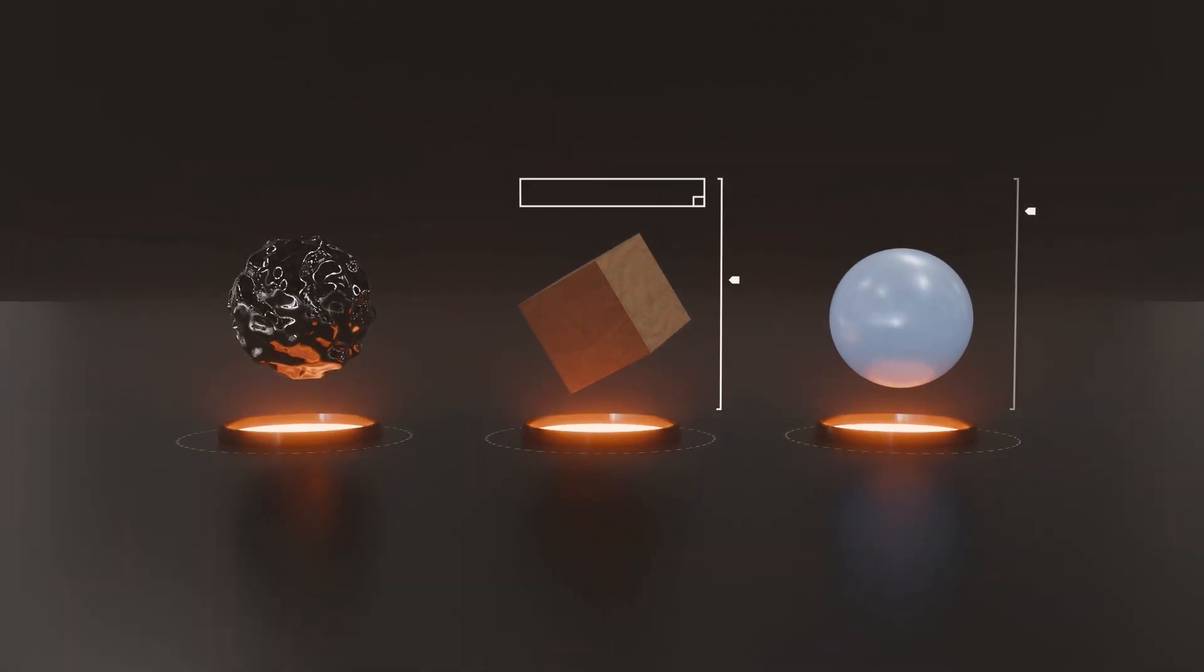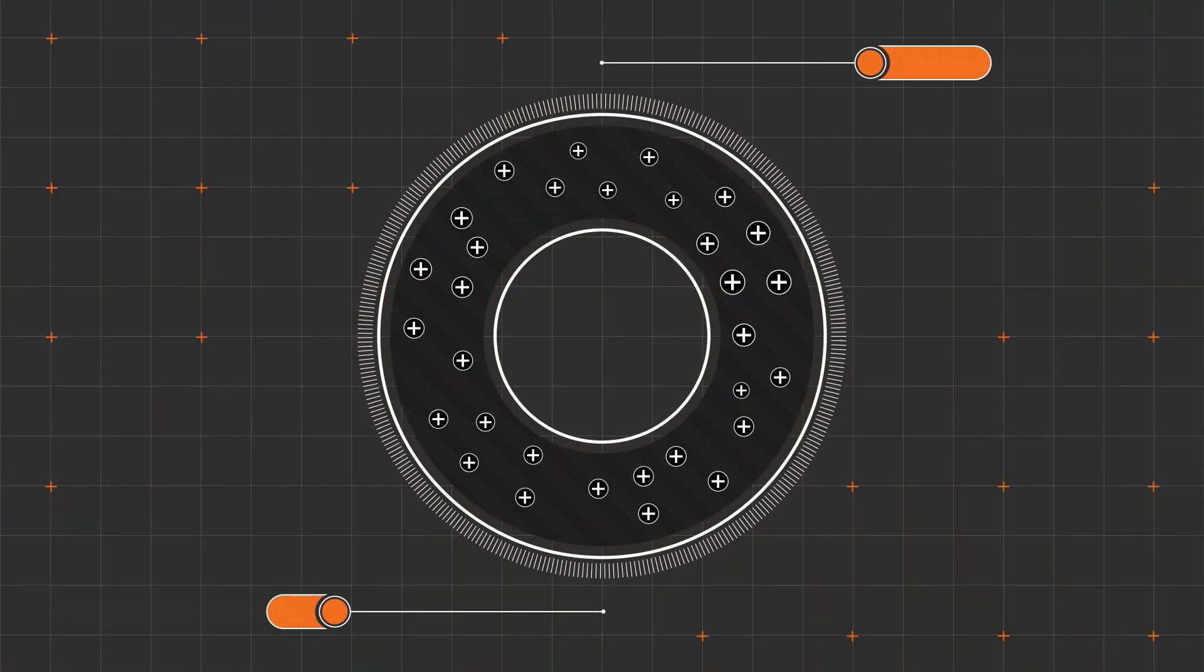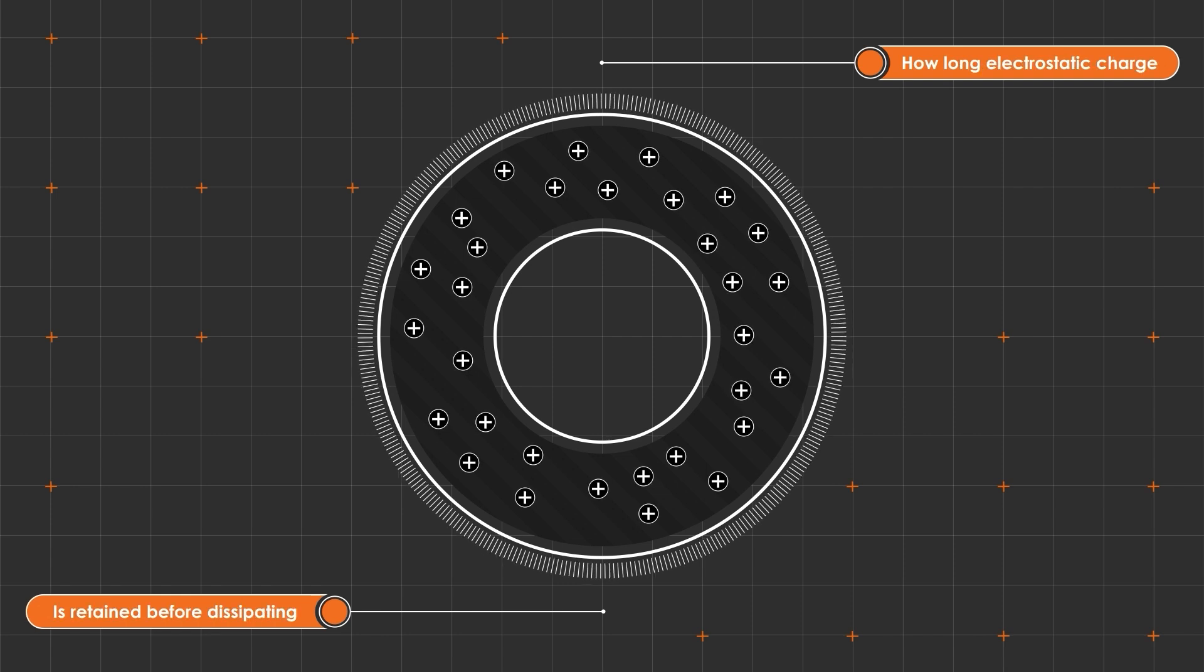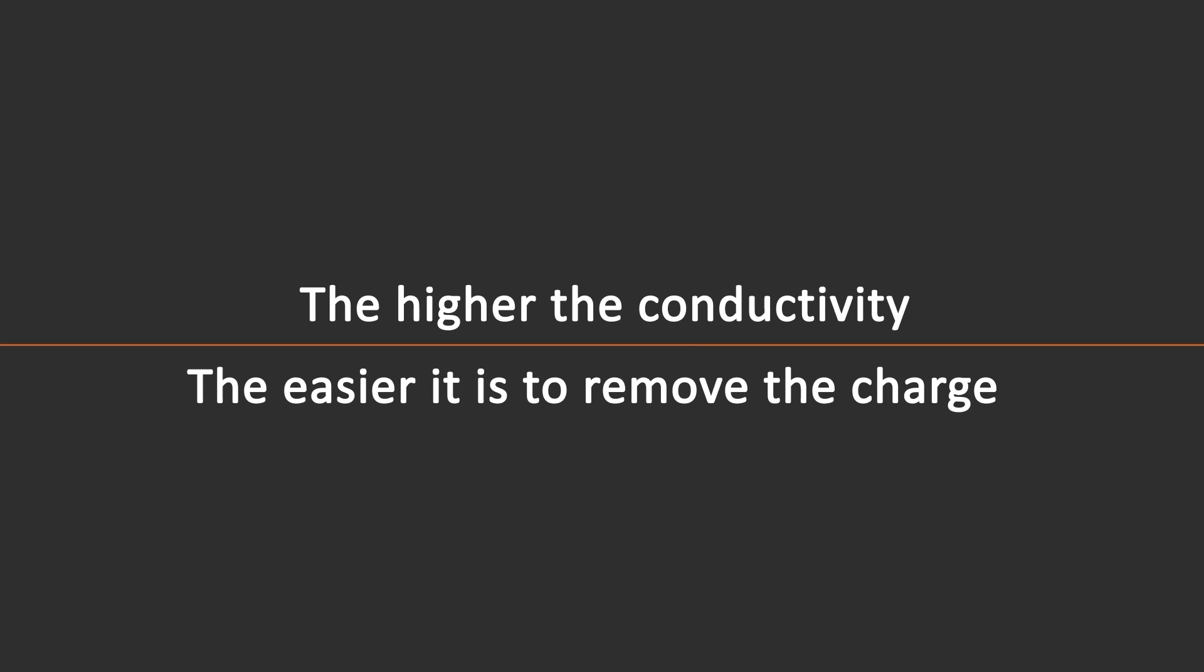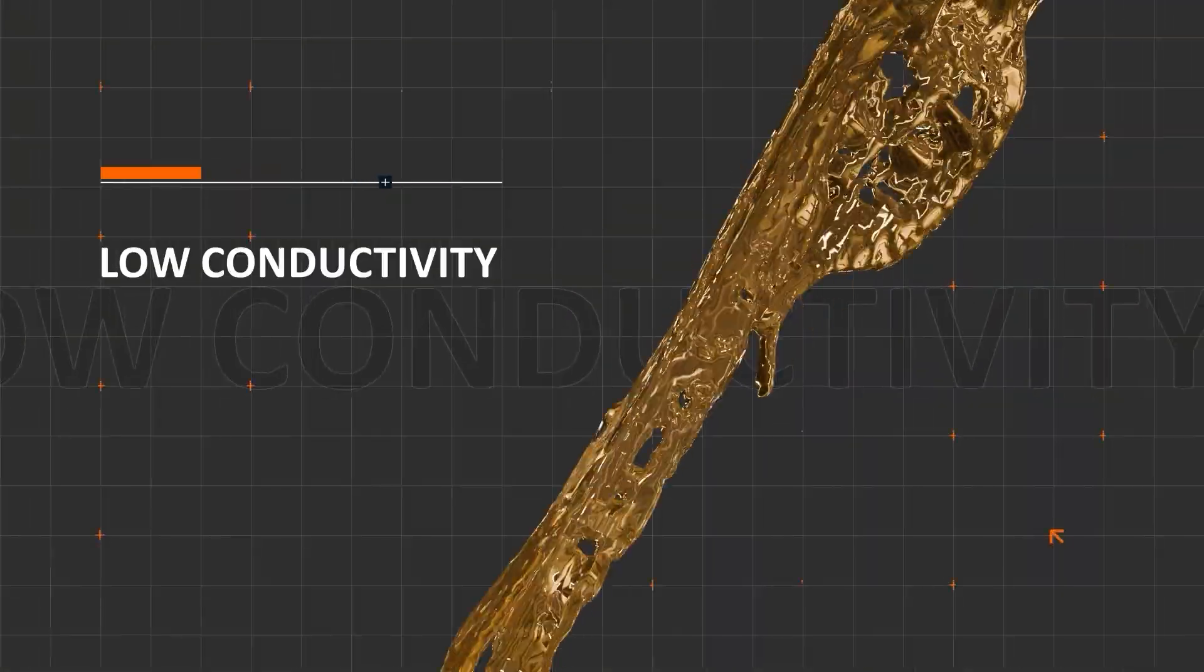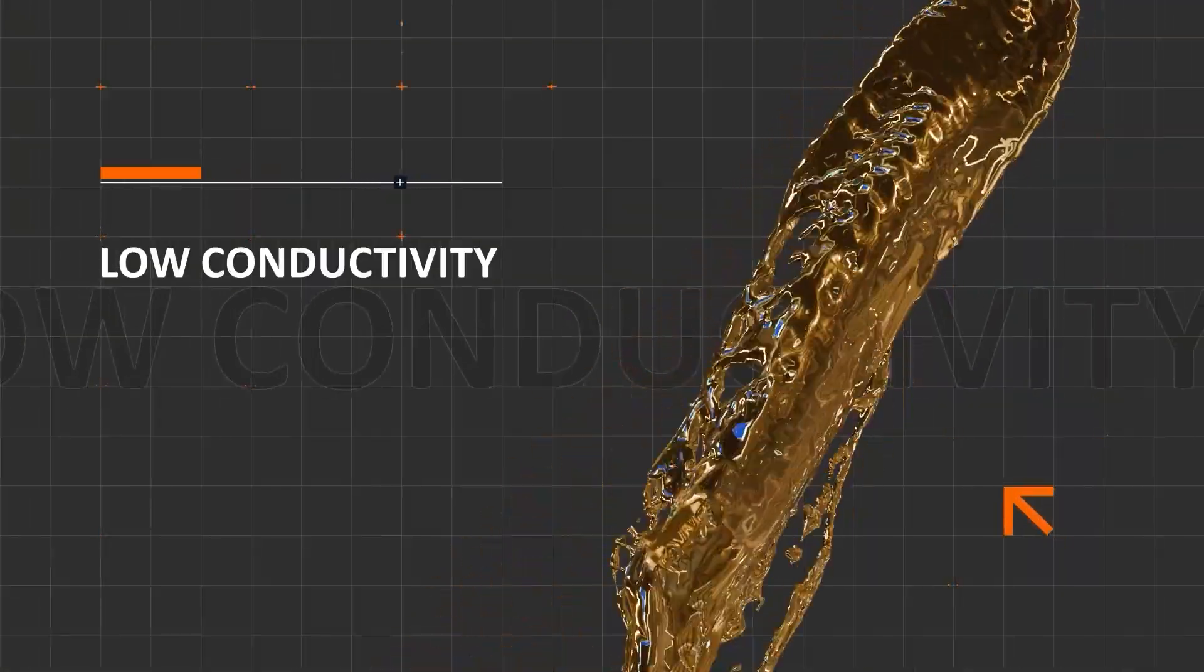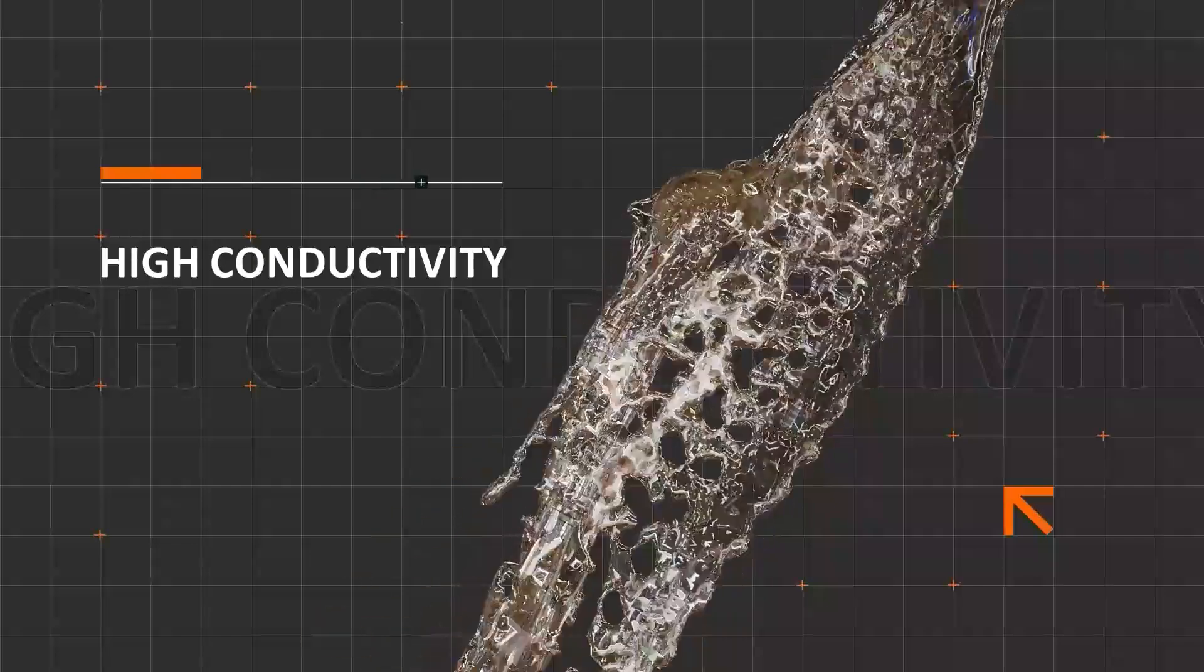Some materials are better conductors of electricity than others. Conductivity is important because it influences how long any accumulated electrostatic charge will be retained before it dissipates to leave the material electrically neutral. The higher the conductivity, the easier it is to remove the charge. Materials are generally classified into low, medium, and high conductivity. Examples of low conductivity materials include lubricating oils. Water is an example of a high conductivity material.